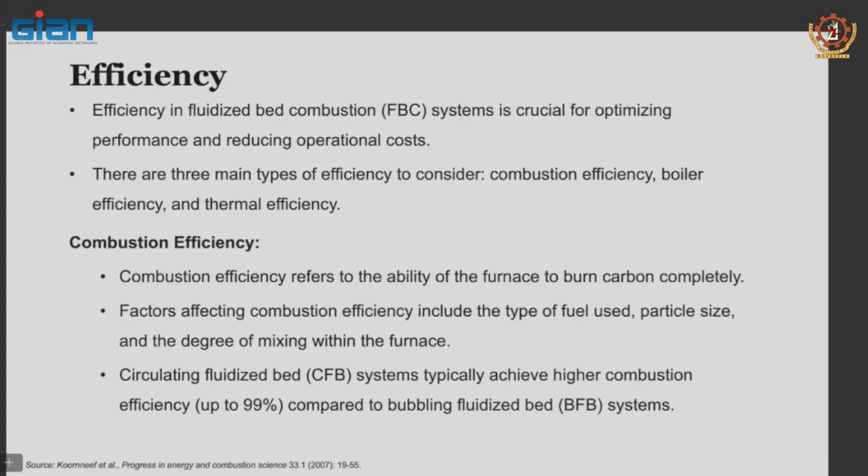So in some systems, for example PC systems, you have to blow steam over these to remove that coating. Otherwise, it prevents heat transfer. In a fluidized bed system, the advantage is that sand particles constantly break off that slag, which promotes better heat transfer. But at the same time, if you have a lot of contact, it erodes the surface and ruptures the heat transfer tubes.